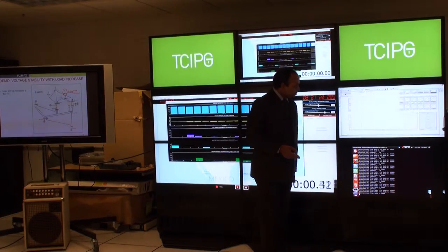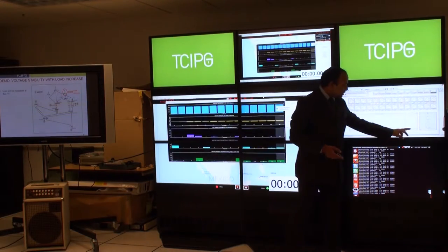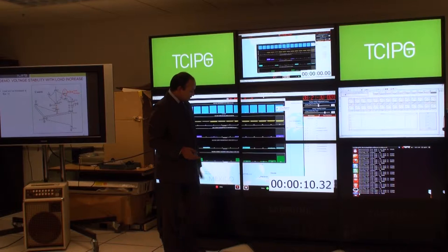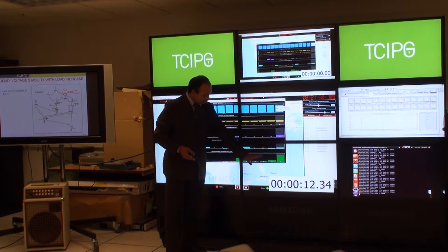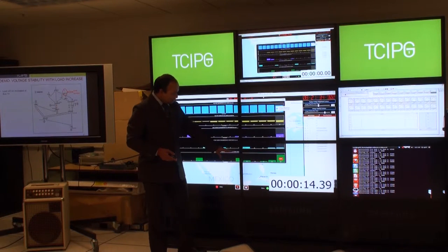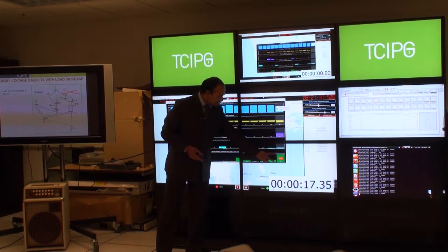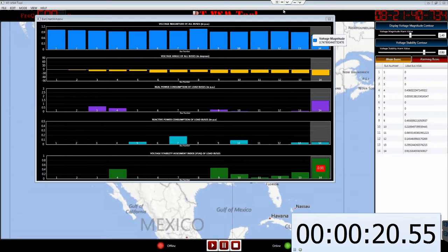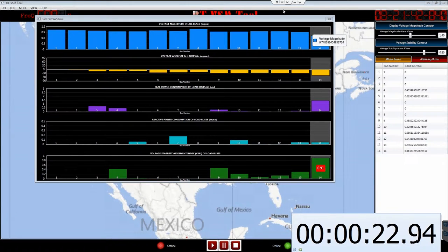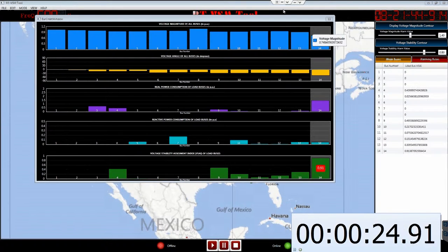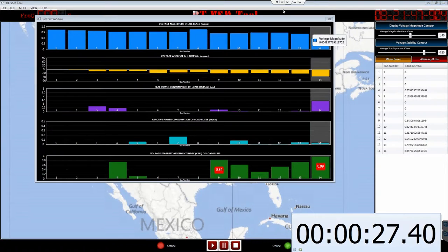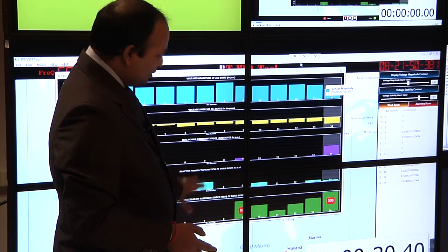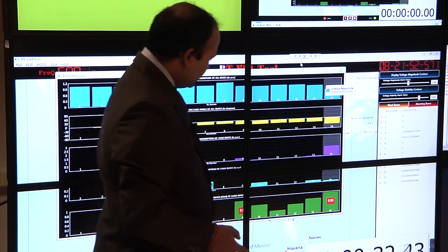We are going to watch how this changes if we make changes in the load. We will run the script file. This will change the load from here. You see that voltage is changing here, and you see that being reflected here also. We set the threshold to 0.8, and as soon as it leads to 0.8, it will turn red. You see that voltage instability, which started at one bus, will spread around the system. And that is what you see here happening. That was our normal case.